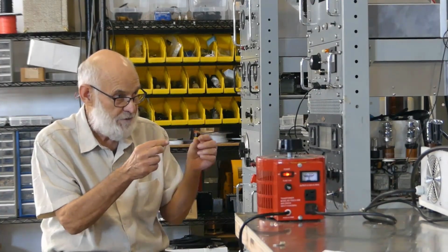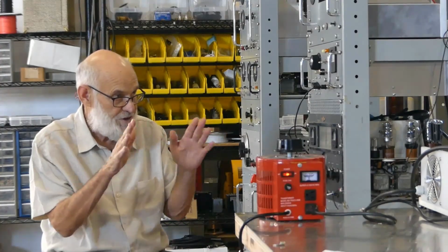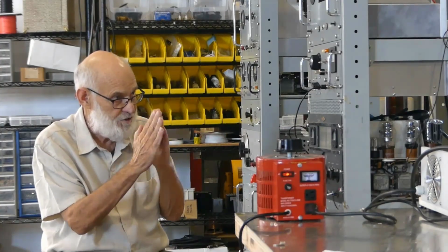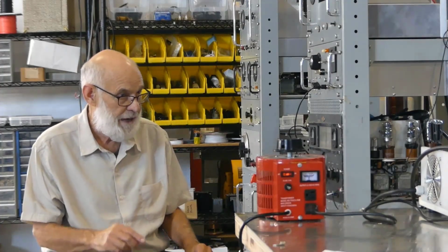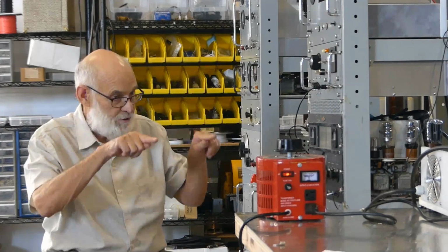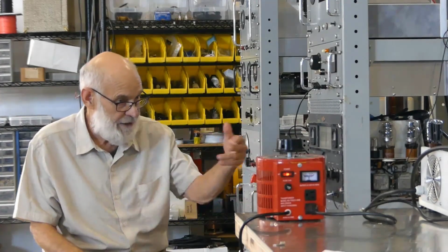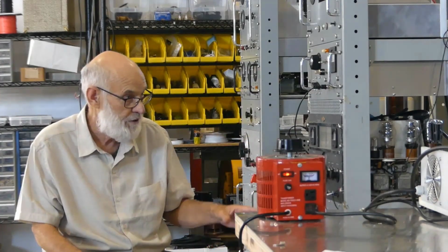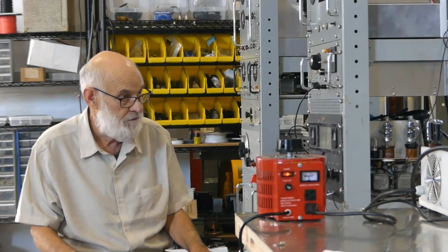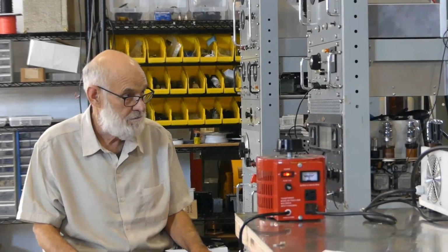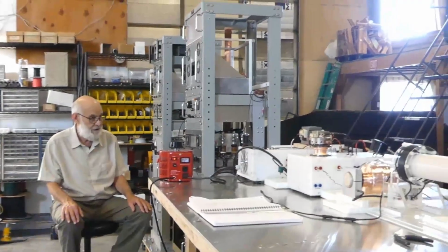That's not good. So the equalizing resistors tend to balance it out because they don't all close at exactly the same time. Then I have an inductive discharge dissipation, a capacitor-resistor series that goes across the contacts, so any back EMF from any coils doesn't keep that arc going and damage the relay. And those ballast resistors will be in series with each of the relay contacts.